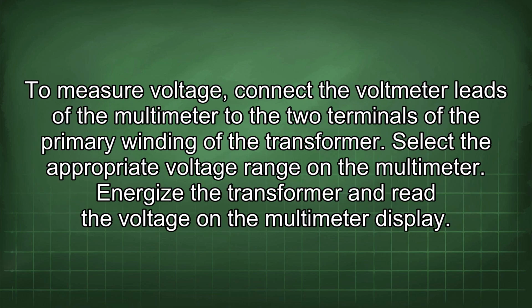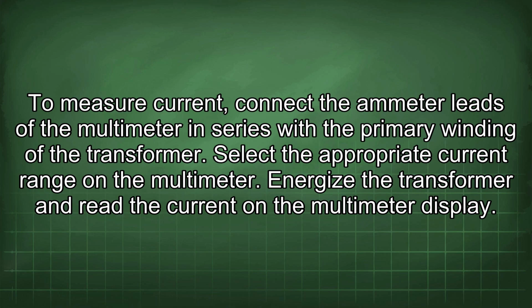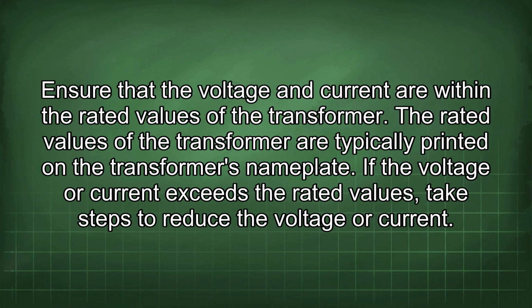To measure voltage, connect the voltmeter leads of the multimeter to the two terminals of the primary winding of the transformer. Select the appropriate voltage range on the multimeter. Energize the transformer and read the voltage on the multimeter display. To measure current, connect the ammeter leads of the multimeter in series with the primary winding of the transformer. Select the appropriate current range on the multimeter. Energize the transformer and read the current on the multimeter display. Ensure that the voltage and current are within the rated values of the transformer. The rated values of the transformer are typically printed on the transformer's nameplate.